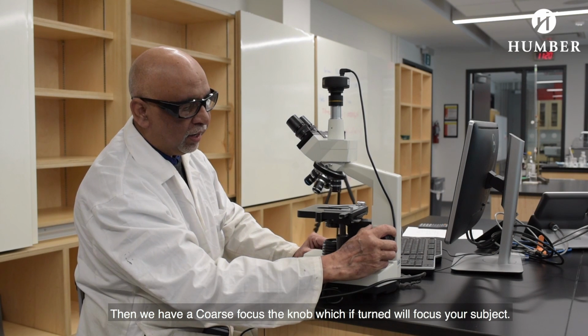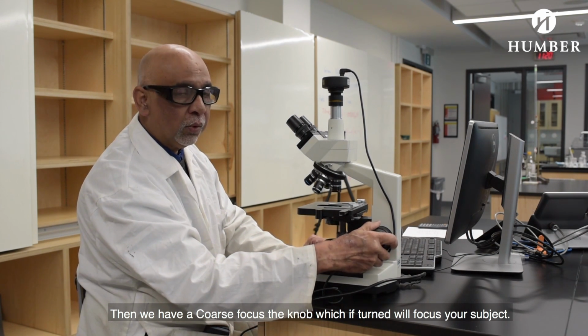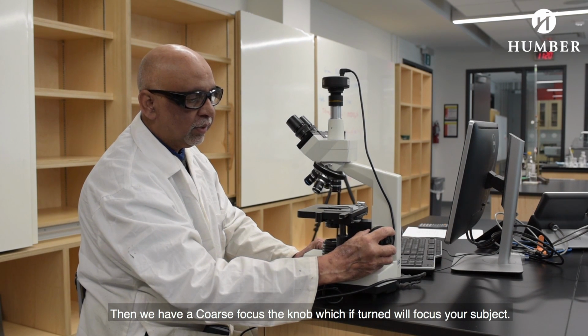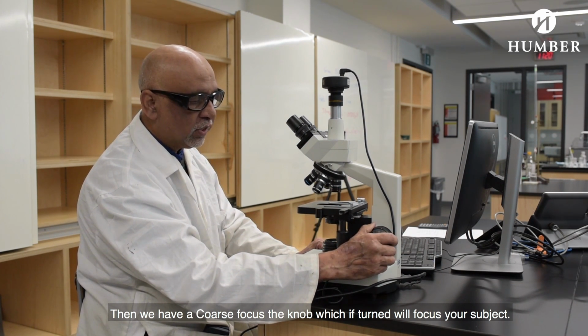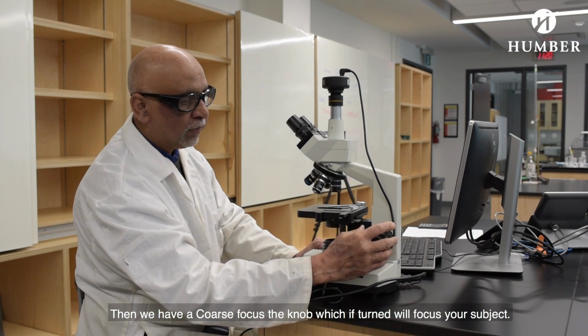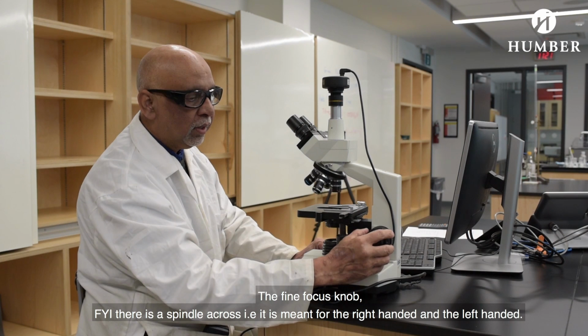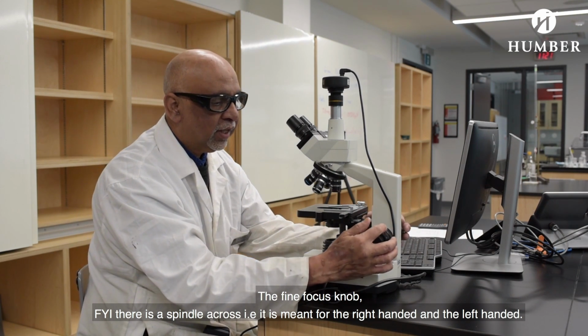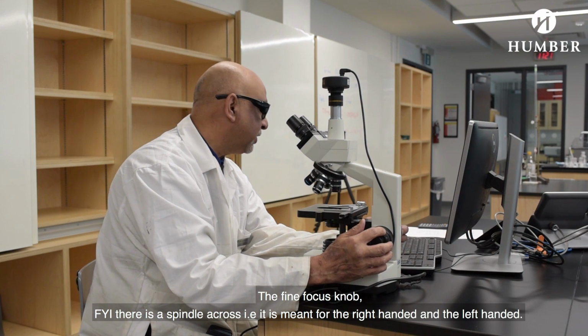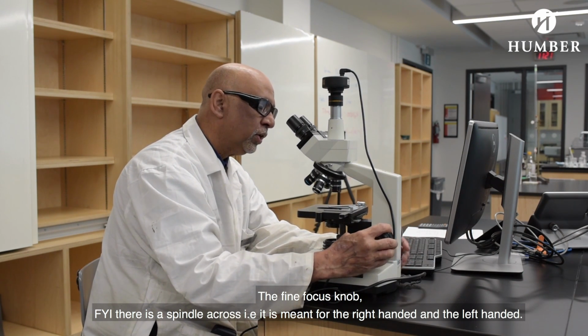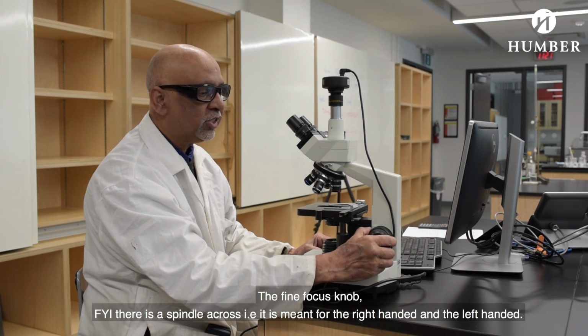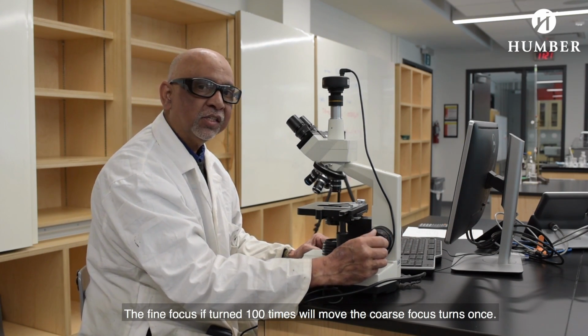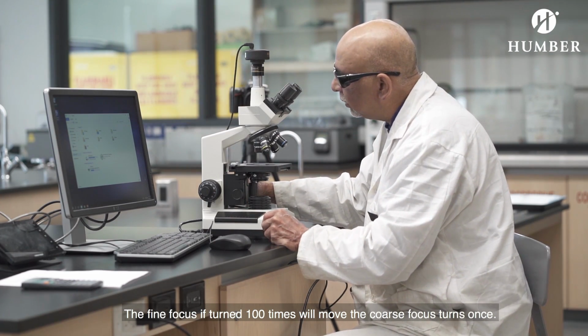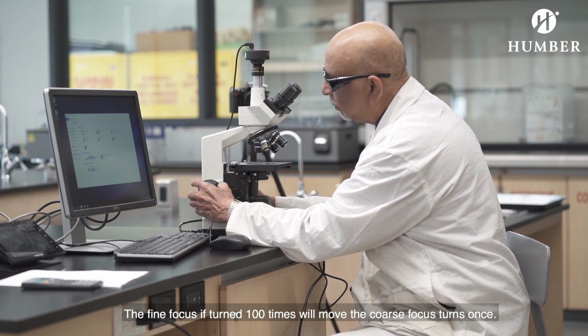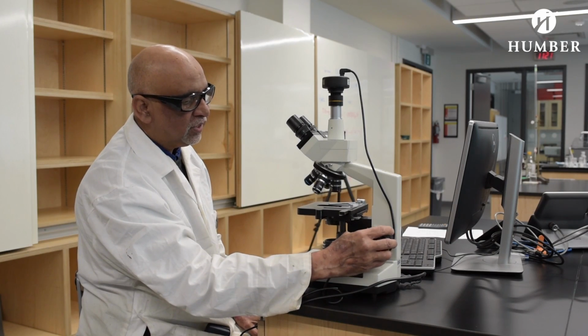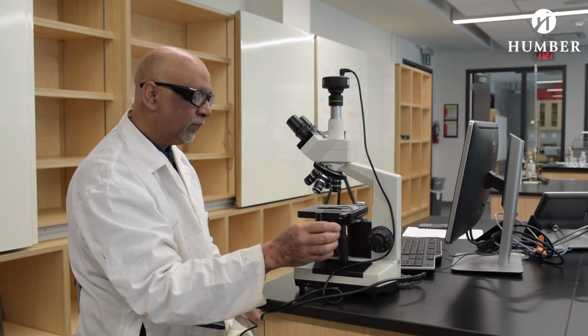We then have a coarse focus knob, which if you turn it, will focus your subject as you need. We have a fine focus knob. Just for your information, there is a spindle which goes across. That means if we turn the coarse, the left hand and the right hand are the same. The fine, if you turn this 100 times, the big coarse knob turns once. So this is as far as the focusing goes.